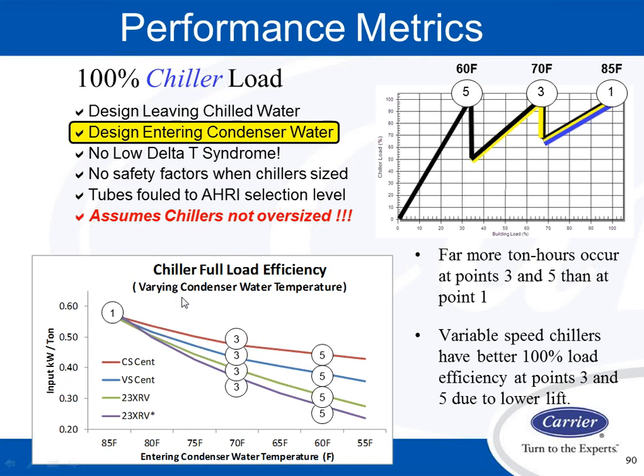You can see that in this following piece here where we have chiller full load efficiency, 1, 3, 5. 1, constant speed machine, it reduces as the water temperature drops, we basically get better in efficiency. Variable speed centrifugal is in blue, gets better. 23 XRV, the machine we just talked about, 1, 3, and 5, even better than a variable speed centrifugal. And then what we have here is our part load optimized 23 XRV, which is the absolute best at 3 and 5.